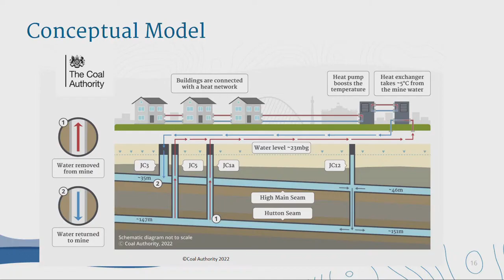The water's pumped out and goes through the heat exchanger. The heat exchanger at Gateshead takes a bit more than 5 degrees out. So that's another thing you can adjust when you're designing these systems, the amount of water temperature you take out. The greater your temperature drop, the less flow you can have. So that can allow you to reduce the flow rates and obviously reduce pumping costs and lifting water costs. So it goes through the heat exchanger and then it goes back underground. So no mine water goes anywhere near the heat pump, and the heat pump then interfaces with the heat network and boosts the temperature. So I'll go into that in a little while.